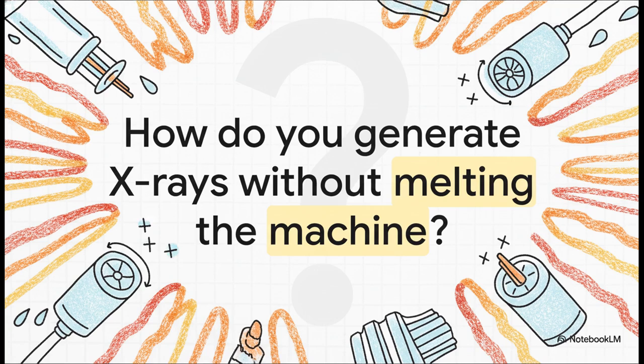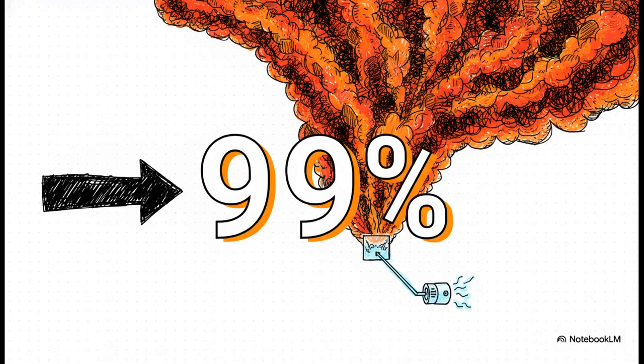Because to get those powerful X-rays we need for modern medicine, you have to generate an absolutely insane amount of heat. Just look at this number for a second: 99%. That's how much of the electrical energy we pump into an X-ray tube is instantly wasted as heat. Just 1% actually becomes the X-rays we want. So, you see, our real job as engineers isn't just making X-rays. It's figuring out what on earth to do with all that destructive heat.